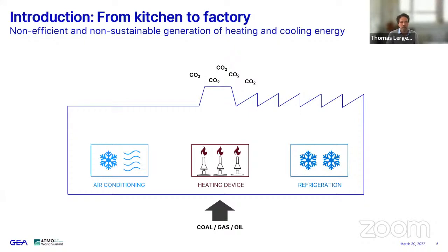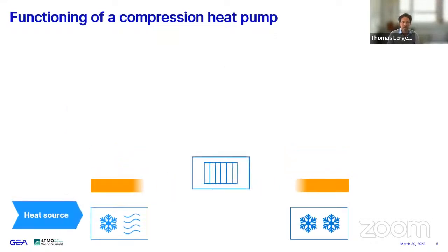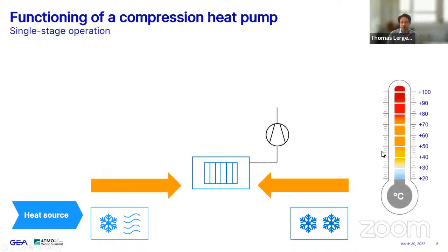And how does it work? How does the heat pump work in this context? For a heat pump you need a heat source. And you can take, for example, waste heat from cooling devices, from refrigeration plants, and use that in your heat pump. This goes into the heat pump and lets the refrigerant evaporate due to the heat transfer. And then the refrigerant is compressed to a higher temperature and pressure level, where it then condenses.